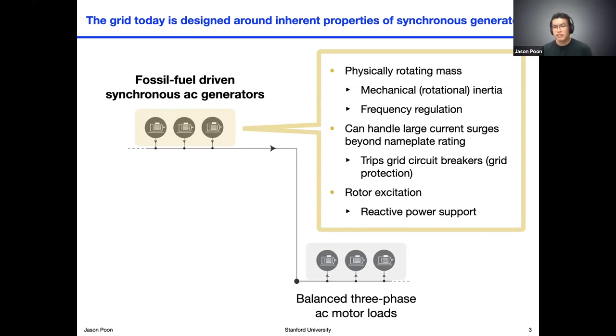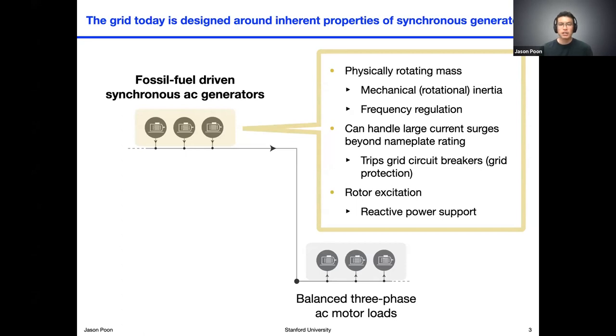That's really important because when faults occur on the grid, such as a short circuit fault, synchronous generators can provide this very large surge current. Various protection mechanisms on the grid are carefully looking for these surges in current to either trip a circuit breaker or activate their protection mechanism. Finally, reactive power support is a very important control mechanism of the electric grid today, enabled very easily with synchronous generators simply by changing the excitation of the rotor.